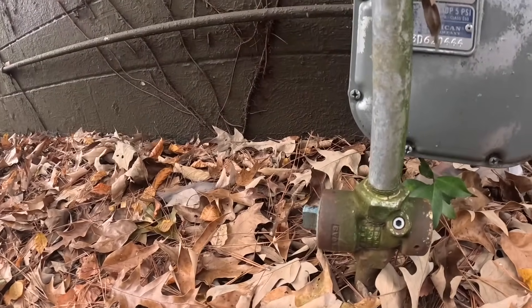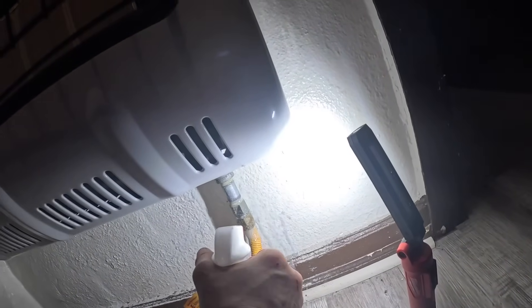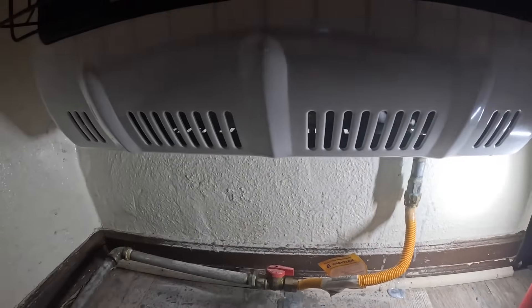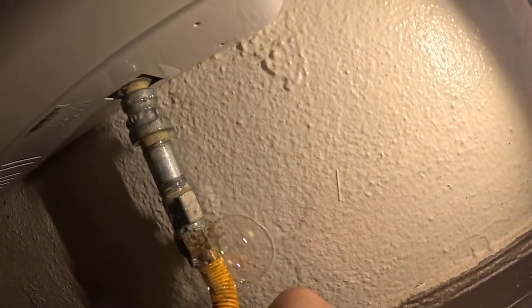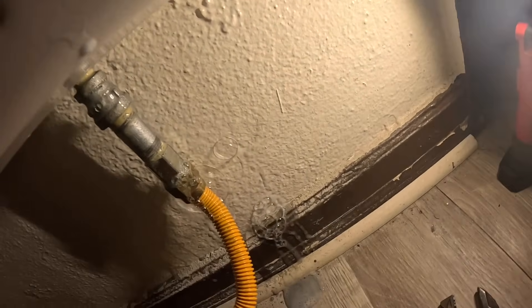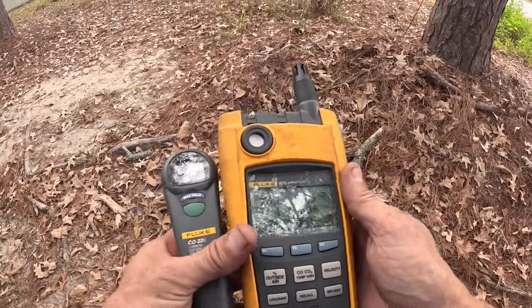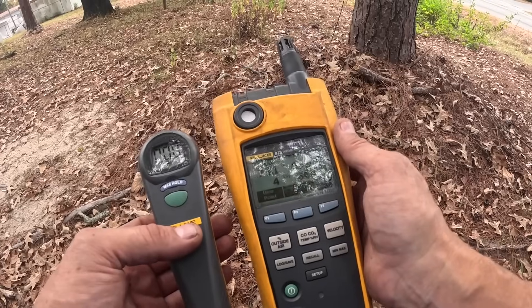This has turned so it's facing up and down. Right now I'm bleeding the gas lines because there's air in them — I'll bleed until I can smell the gas. Outside I'm reading four on this one and nothing on the other.